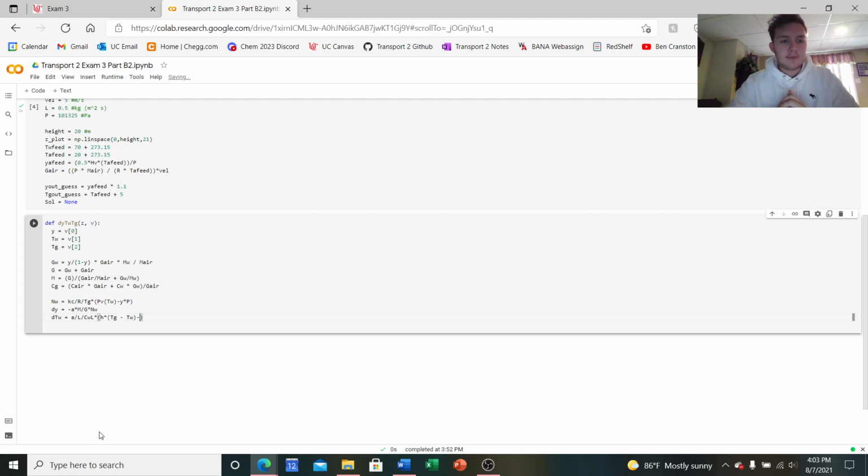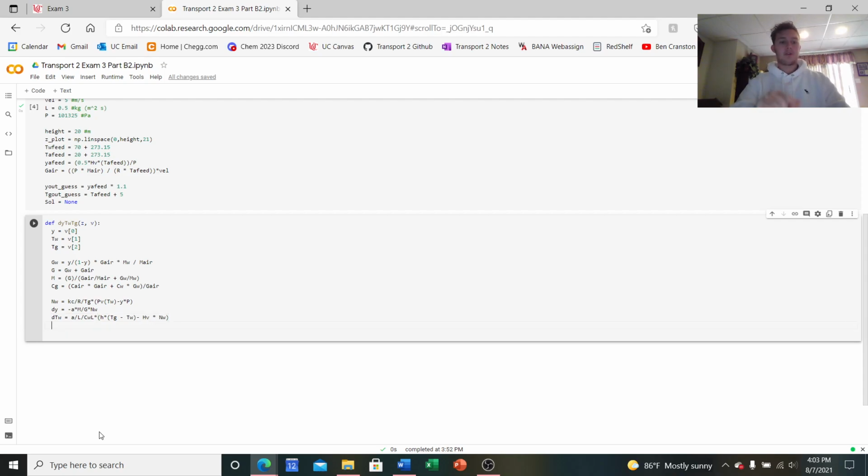second set of values and variables that we had previously, where I explained how this is going to have to be added on to account for the heat and the mass lost to evaporation through this transfer. As the hot water transfers down the tube and through the cooling tower, it's going to be cooling off, and so you have to account for some of that mass being evaporated off. This is really coming from the heat of vaporization value multiplied by the molar weight that we found as well. So that's the second differential equation.